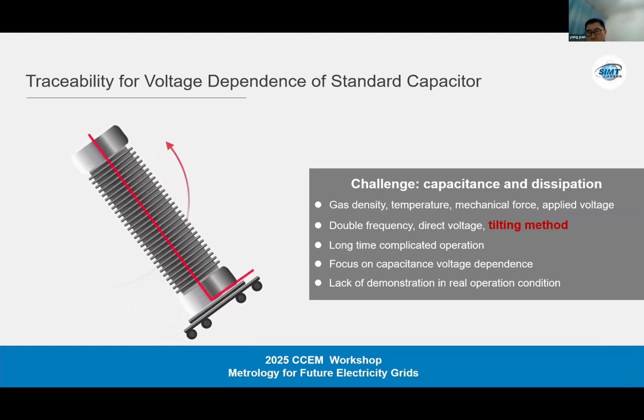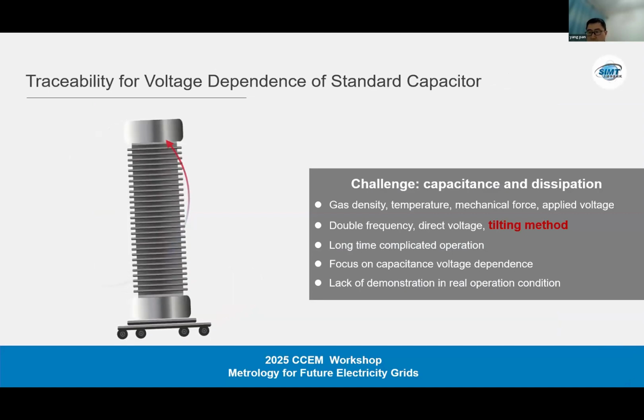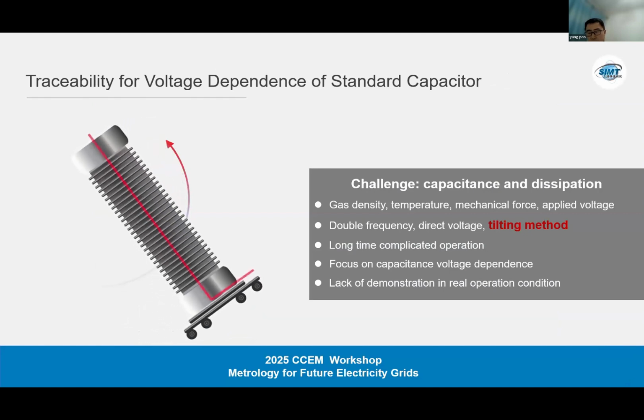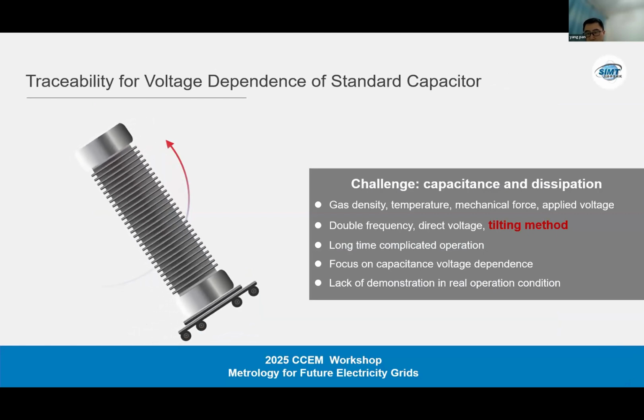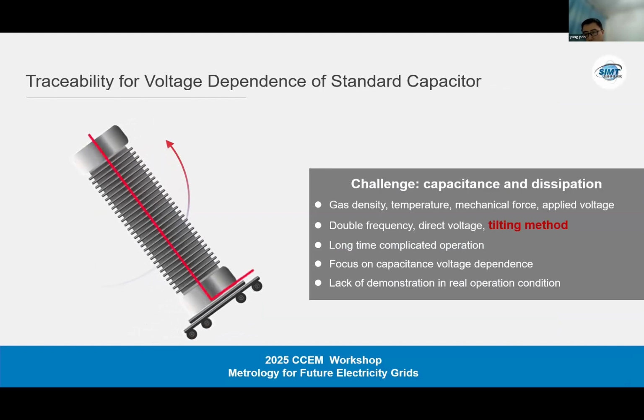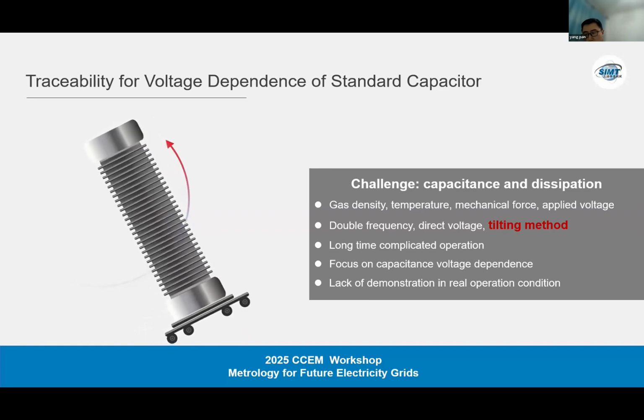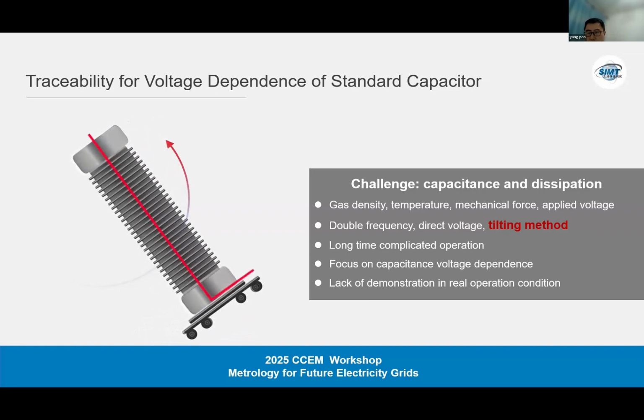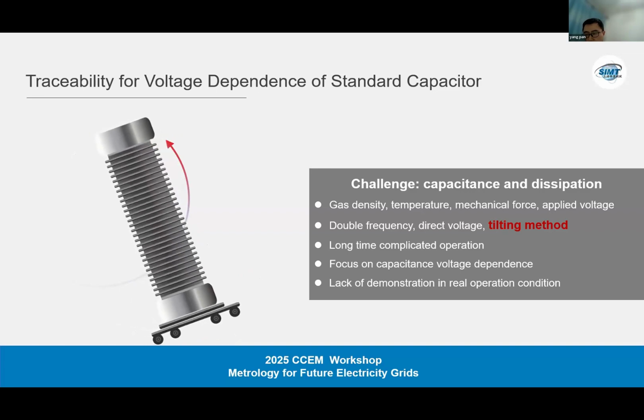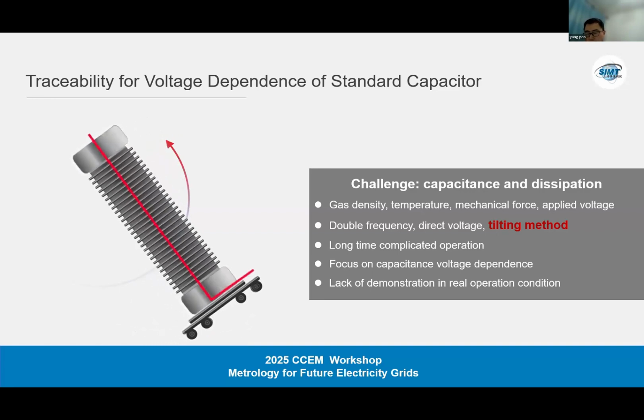It is worth noting that all digital measurements are ultimately traceable back to analog quantities. In the case of voltage transformers, most national metrology institutes still perform traceability through measuring the voltage coefficient of compressed gas capacitors. At this point, I would like to briefly mention the advancements China has made in this field. So eccentricity of the electrode alignment, induced by electrode position and geometry variation, is considered to be the main contribution to the voltage dependence of this kind of compressed gas high voltage standard capacitor.